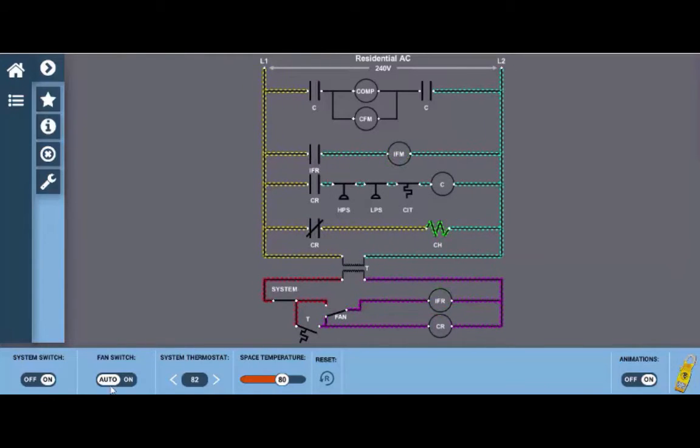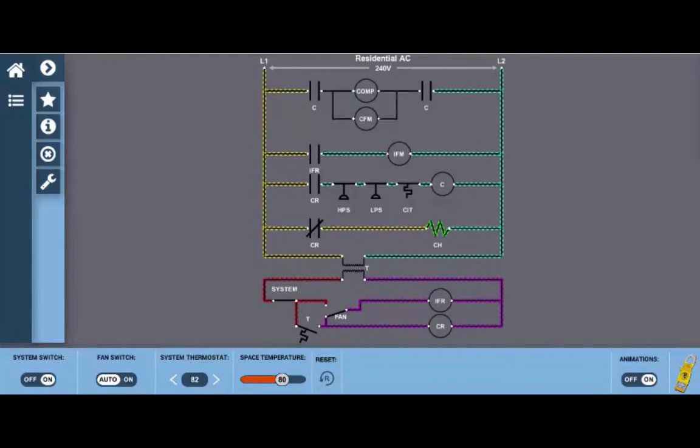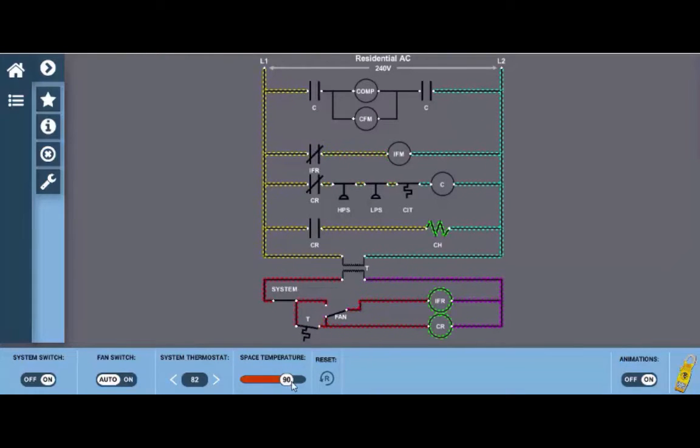Now we're going to go back to the auto position. With the fan switch in the auto position the indoor fan relay will only energize and operate the indoor fan motor when there's an actual call for cooling. So we're going to do that. In order to call for cooling we need to set the system thermostat down below the space temperature or you can use the slider and turn the space temperature up above.